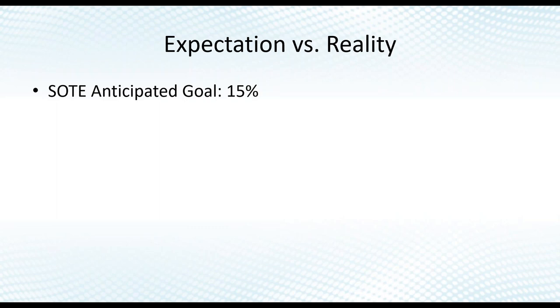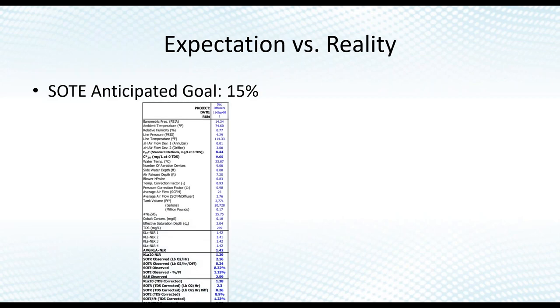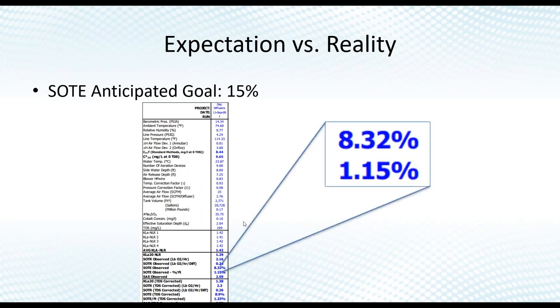We were looking for 15% efficiency. We were confident — we thought we'd do 16% because we had fine bubble. We went through the testing, got a whole bunch of variables, and then saw the numbers: 8.3% and 1.15% per foot. It took a little time for it to dawn on me that the 8.3% was what we were hoping would be 15%. Despite all the research and dozens of hours of engineering time, this was what we were actually getting.